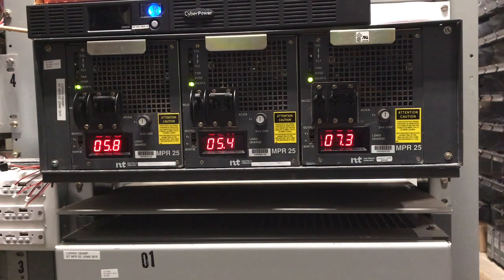And they can be anywhere from 30 amps up to 1,000 amps or so, depending on the office. I've installed equipment in buildings that had 1,000 amp BDFBs, lots of them, and when you're working in the rear of those, of course it's all maintenance window work. You're working in a power system that's got 1,000 amp potential, which if you ever make a mistake, you have an explosion, you weld things, start fires, bad situation within milliseconds.